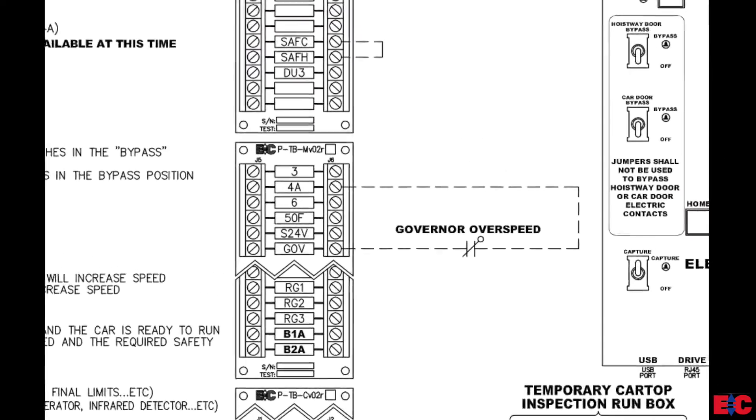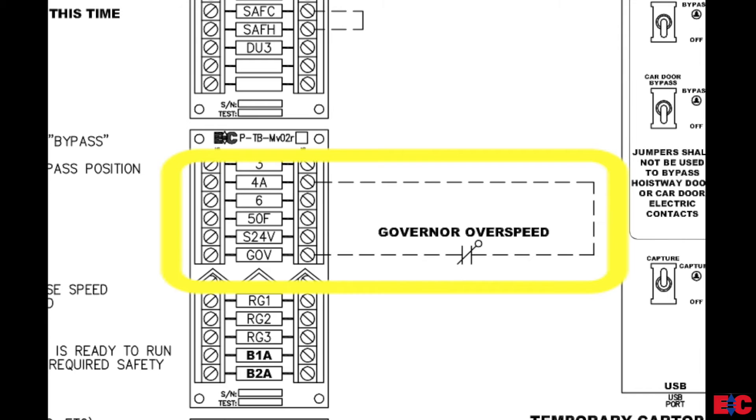On the machine room terminal board, we want to wire up the governor overspeed switch between 4A and GOV.